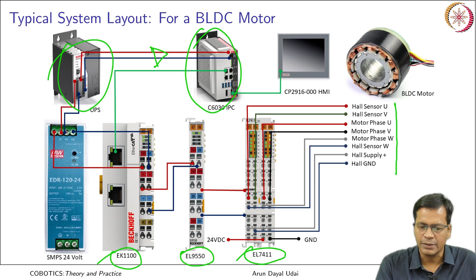The first thing is your IPC, that is the industrial PC. The next one is your EtherCAT coupler. The third one is the power filter device, and then come the other input output cards and the servo motor drives. So everything else can go there. Altogether, one EtherCAT coupler supports 65535 such cards. So overall the layout may look like this. This is your CPU, the one that I have shown. This is the UPS to maintain a constant supply to this CPU and other devices. This is the EtherCAT coupler, this is the power surge protection device, and here comes your BLDC motor driver, and all the connections are shown here. That includes the motor phase wires UVW and the Hall effect sensor wires. If the motor has a brake wire also, this servo drive supports that.